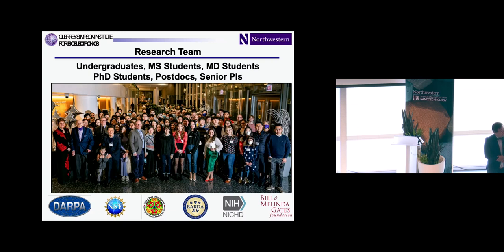So we had to move to a different engineering design that embeds batteries and wireless recharging capabilities directly into the device, and offers a level of physical robustness that allows for hundreds of cycles of use, so you can amortize the cost of the device out of the cost per patient monitoring day. And so that was a driving consideration to meet the requirements in LMICs that required a shift in some of the engineering aspects.